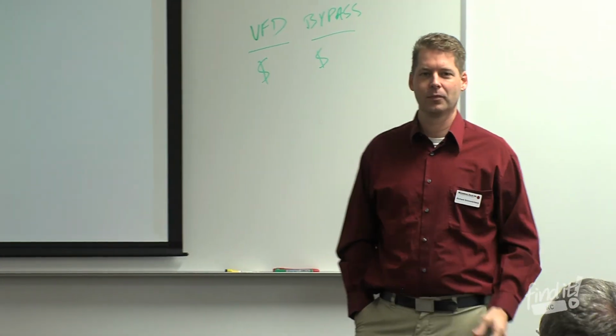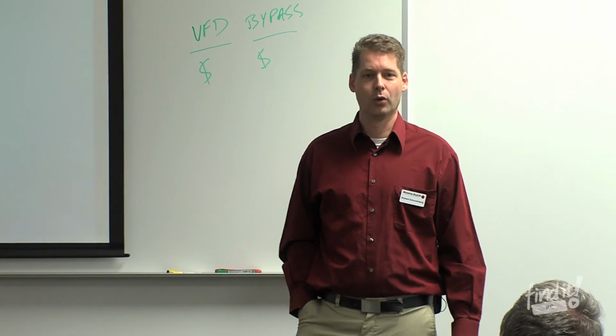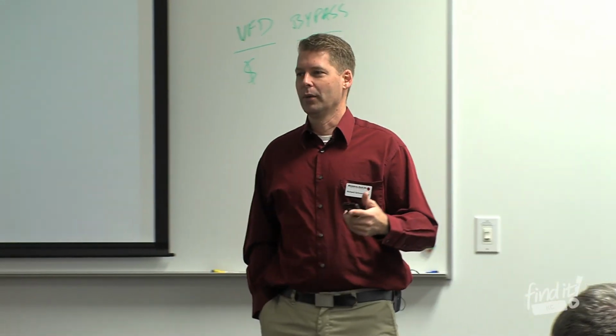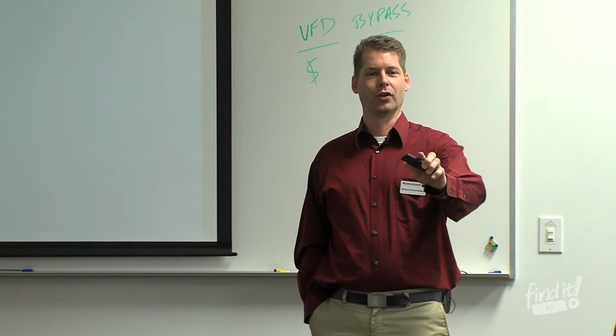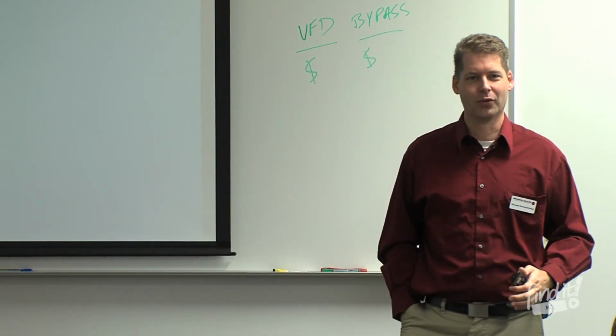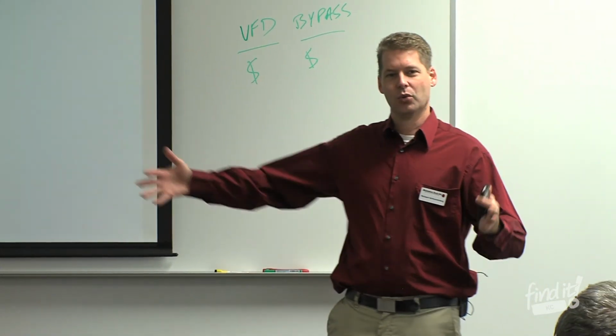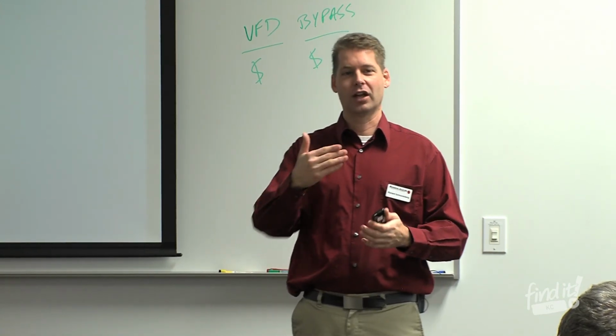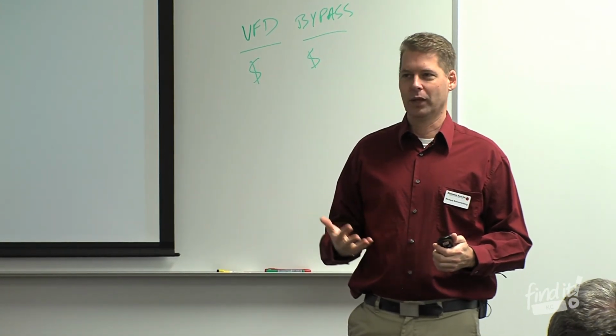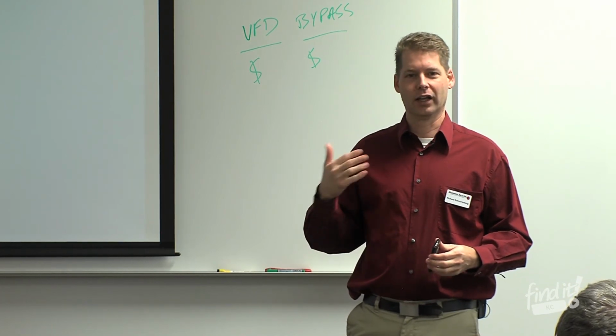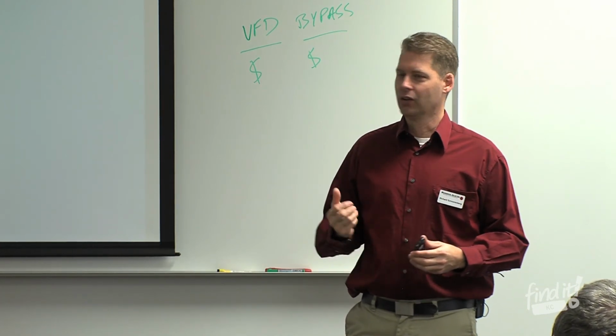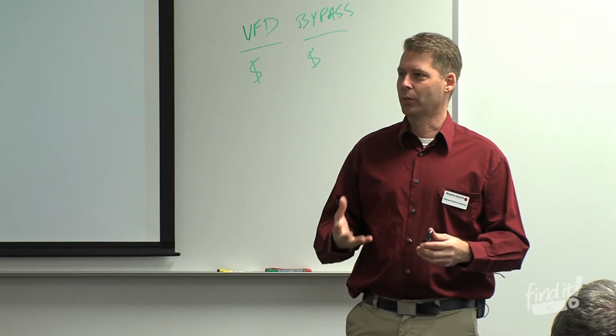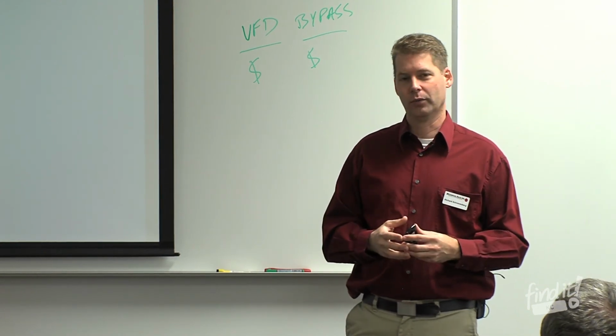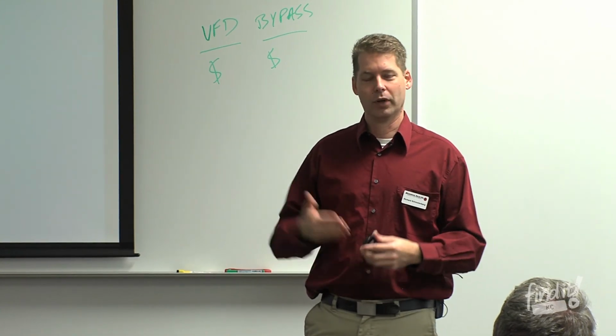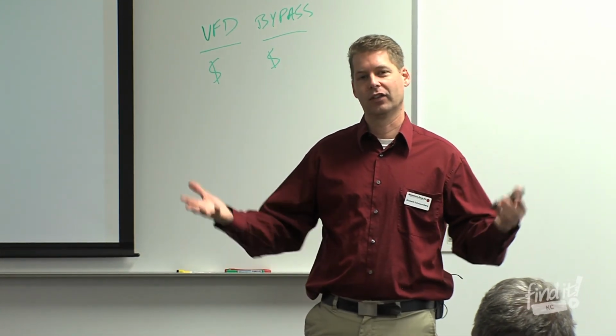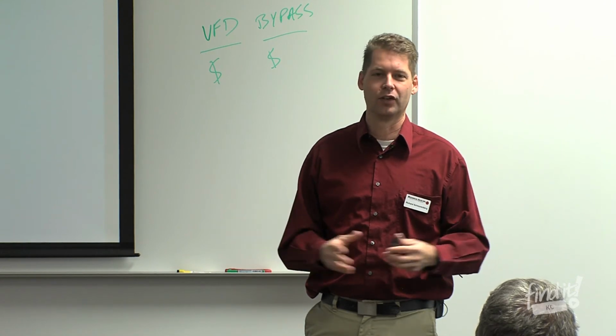If you're running more than 10 hours a day, does that shorten your life? Oh yeah. Yeah, so the question was, if you're running more than 10 hours a day, does it shorten the life? I'm sorry, I answered yes before I thought about the question. If you're running more than 10 hours a day, it reduces the dollar amount that you save, but it doesn't actually shorten the life of the VFD. VFD lifespans are mostly limited by the electrolytic capacitors inside the VFD. So the electrolytic capacitors have a usable lifespan, whether they're being used lightly or heavily, 20 hours a day or 10 hours a day. They have a fixed lifespan, and it's usually in the 15-year mark.